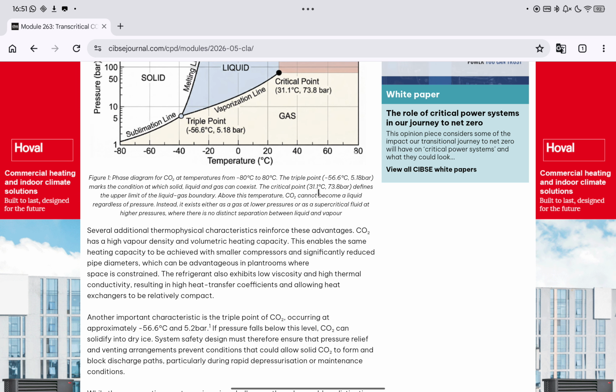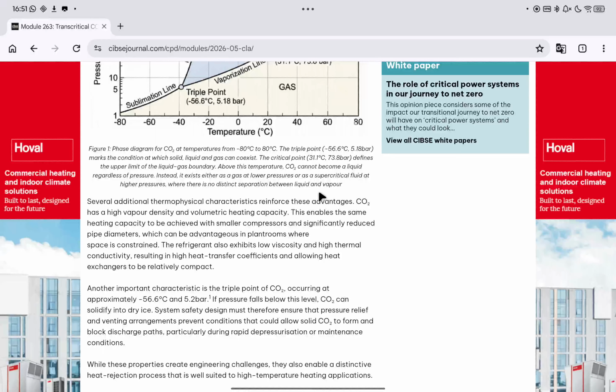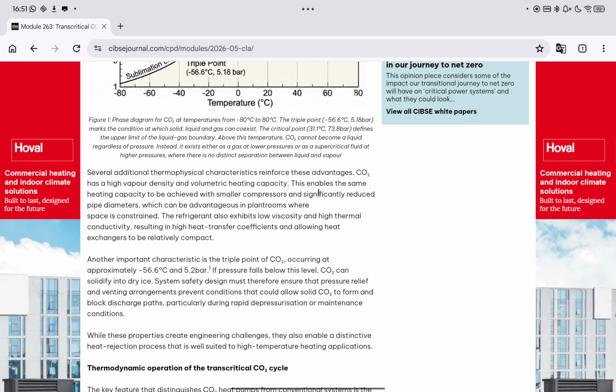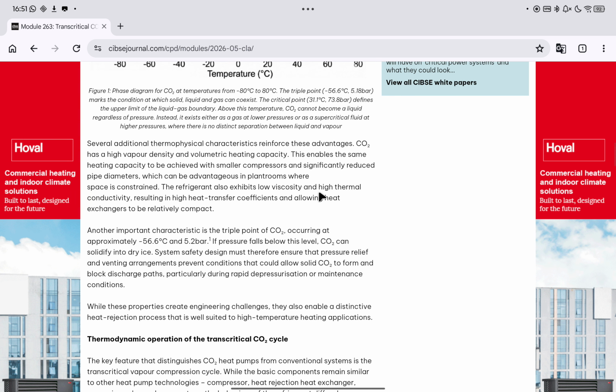to be relatively compact. Another important characteristic is the triple point of CO₂, occurring at approximately minus 56.6 degrees C and 5.2 bar. If pressure falls below this level, CO₂ can solidify into dry ice. System safety design must therefore ensure that pressure relief and venting arrangements prevent conditions that could allow solid CO₂ to form and block discharge paths, particularly during rapid depressurization or maintenance conditions. While these properties create engineering challenges, they also enable a distinctive heat rejection process that is well suited to high temperature heating applications.